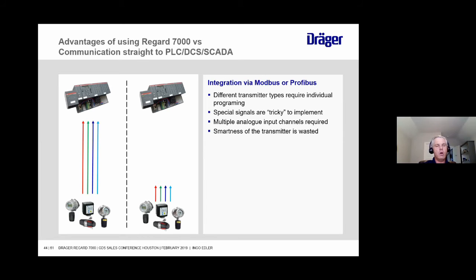So flip to the other example, which is having those different transmitters talk to the Regard 7000 first, and then go into the DCS or the PLC. Like I mentioned, those special signals, if it's a Draeger device, are already pre-programmed in. So when you're configuring the Regard 7000, you say I'm hooking up a Polytron 8700 334 type sensor, and all those special signals are already pre-programmed and just come on over. If you needed to add an extra point, it's very simple. You just hook the point onto the extra module or a spot on one of those modules, and you configure that versus having to program it. Configuring is just drop-down menus, versus spending time programming the DCS or the PLC to take that new input.